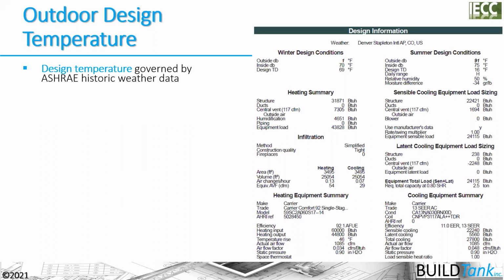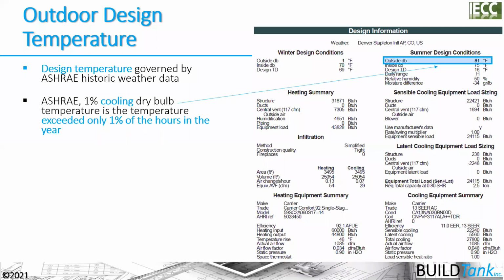Now, the outdoor design temperatures are also created by ASHRAE, but they're created per climate zone or weather district, dependent on weather data that's been looked at over the course of about 30 years or so. In the cooling season, the dry bulb temperature is the temperature exceeded only 1% of the hours of the year. So in Denver, Colorado, for example, we have a design temperature of 91 degrees for our summer conditions. That means that only 1% of the hours over the course of the year does the outside temperature get hotter than 91 degrees.